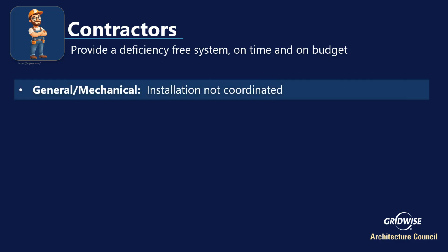The prime contractor, whether general or mechanical, needs to coordinate the installation. When I was in the field, I'd often have to manage up. I'd take the schedule issued to me that gave me 3 working days to do a complete installation, checkout, and sequence test of a 40,000 CFM custom energy recovery unit, and actually add our real schedule. For those of you not familiar, that takes a lot more than 3 days.